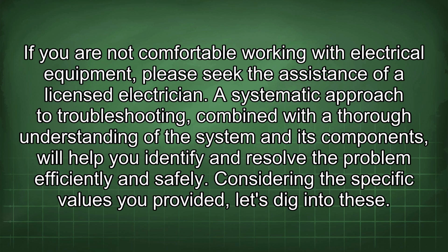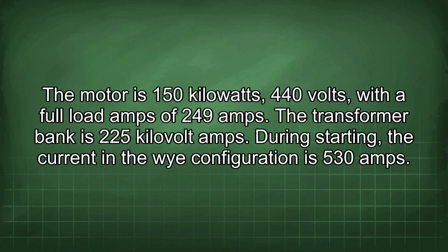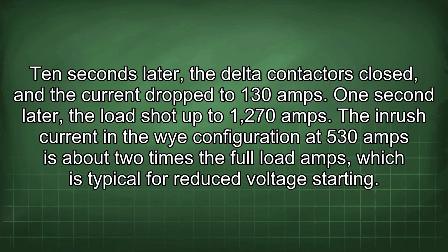Considering the specific values you provided, let's dig into these. The motor is 150 kilowatts, 440 volts, with a full load amps of 249 amps. The transformer bank is 225 kilovolt amps. During starting, the current in the Y configuration is 530 amps. 10 seconds later, the Delta contactors closed, and the current dropped to 130 amps. 1 second later, the load shot up to 1270 amps.